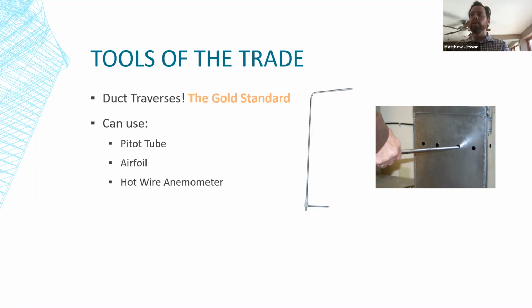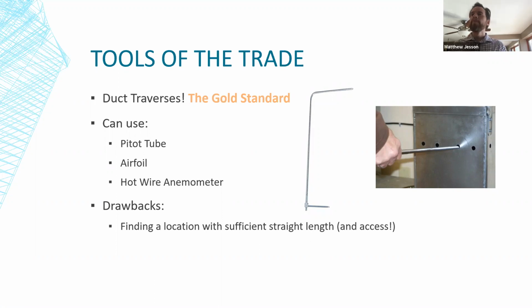And the hot wire anemometer is another instrument that some use, operating on a thermal dispersion principle. The only issue that I'd bring up with the hot wire is that most hot wire anemometers do not know what direction the air is flowing. It just knows the velocity. It could be going the wrong way, and you might not be able to tell just by a velocity reading. Again, depending on the particular model. The only real drawback to a pitot tube duct traverse is you have to find a location for one. You have to have enough straight length, and you have to be able to access it.